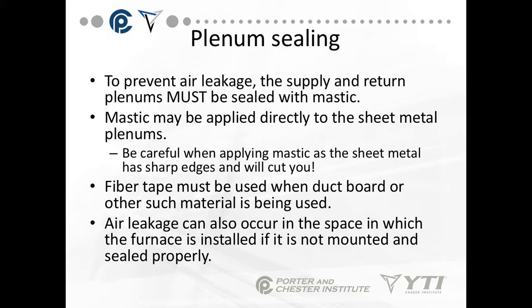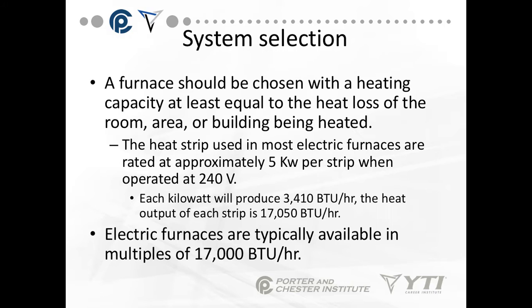Air leakage can also occur in the space in which the furnace is being installed if it's not mounted and sealed properly. To select a system, the furnace must be chosen with a heating capacity at least equal to the heat loss of the room, area, or building to be heated. Electric furnaces are typically available in multiples of 17,000 BTUs per hour. Every kilowatt will produce 3,410 BTUs per hour.